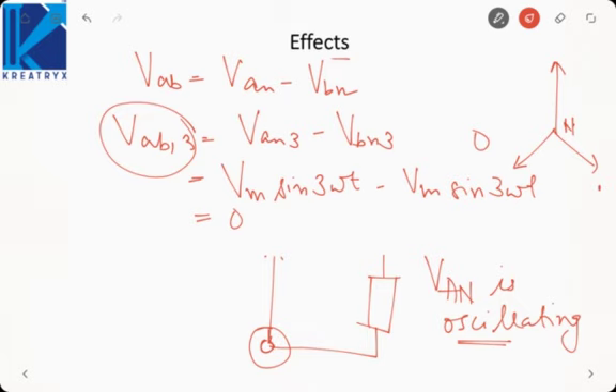Again I am repeating, in a star connection, the phase voltage contains third harmonic, but the line voltage does not contain any third harmonic. So when we connect a three phase load, there is no issue because the line voltage has no third harmonic. But if we connect a single phase load, phase voltage will be applied across that load, due to which the phase voltage will be fluctuating due to third harmonic, and the load will experience fluctuations which is undesirable. This is called floating neutral or the oscillating neutral. So let us see how to remove the third harmonic.